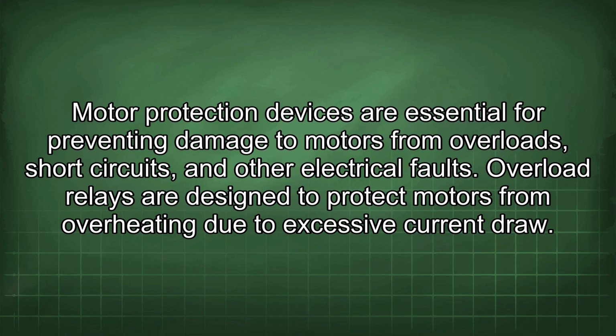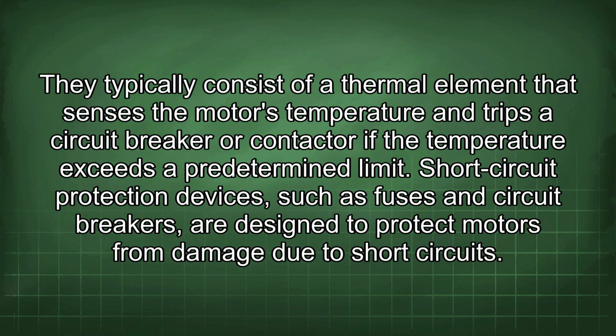Motor protection devices are essential for preventing damage to motors from overloads, short circuits, and other electrical faults. Overload relays are designed to protect motors from overheating due to excessive current draw. They typically consist of a thermal element that senses the motor's temperature and trips a circuit breaker or contactor if the temperature exceeds a predetermined limit.